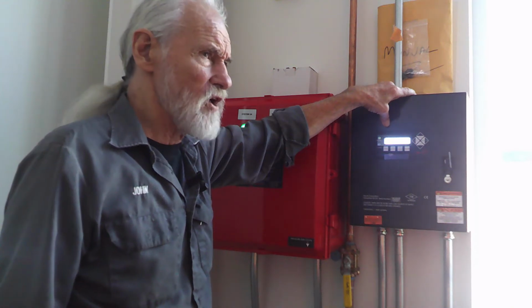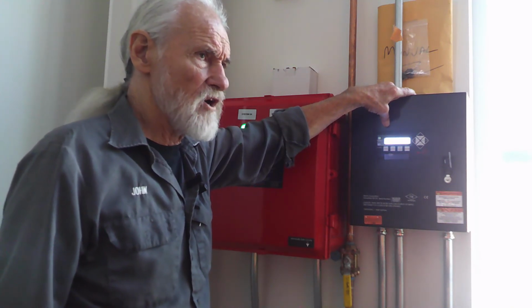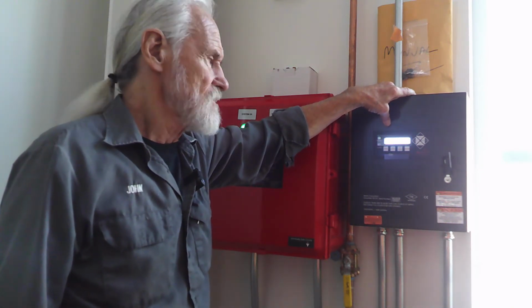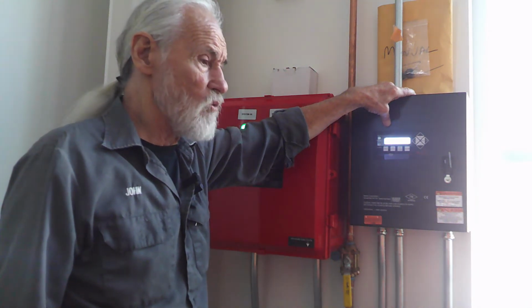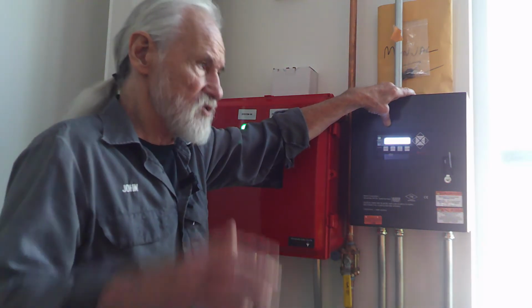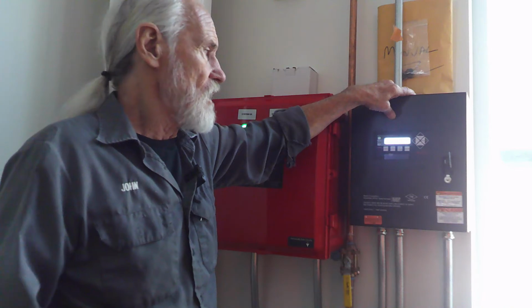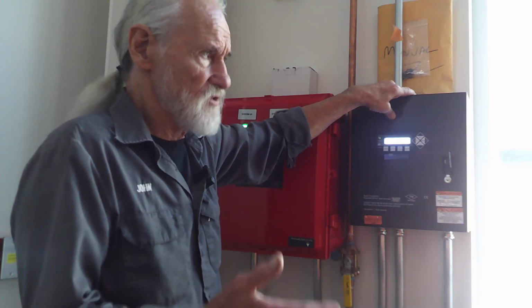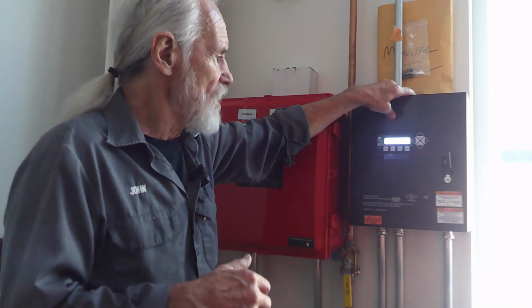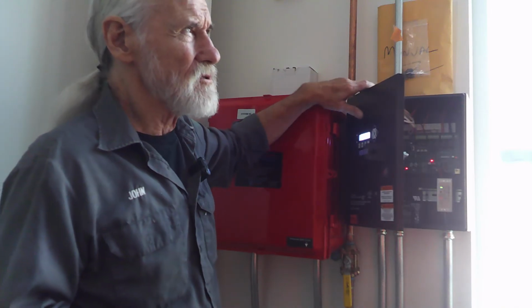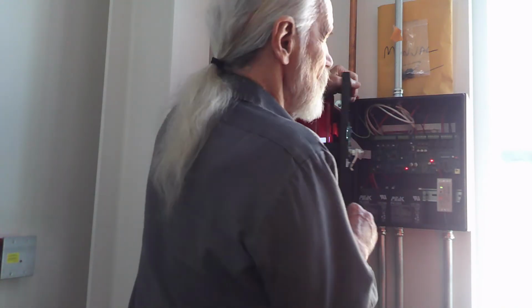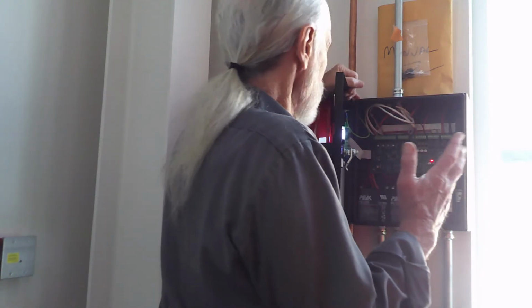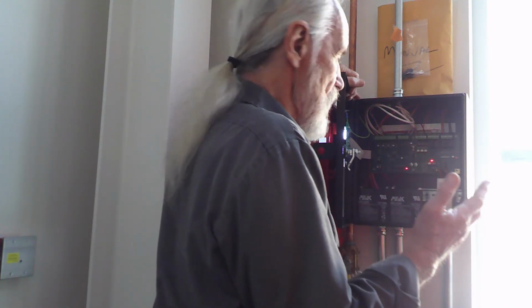You know they test flow in this system? If the flow moves, it'll set it off. Some systems test it this way: if the water starts to move, that means there's a fire somewhere. I've tested it, so I know it works. It runs for, I think, the test mode is like half a second or so. There's considerable pressure on those things, it dumps a lot of water all of a sudden.